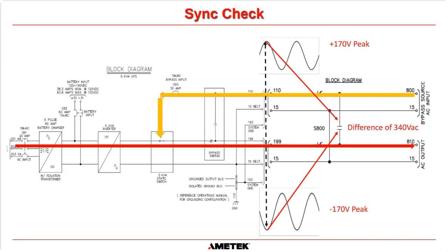Now, what this slide is there to show you is what the bypass switch does: it closes this contact here before it then opens this contact. Sorry, not that contact. It closes this one and then it opens this one. So it is making this contact. And if this point here and this point here has a voltage difference of 340 volts, when you close that contact, high circulating current will flow from the bypass supply back into the inverter bridge and could cause damage to the inverter bridge, and more than likely it's going to trip the breaker that feeds the bypass supply because it sees the high current.